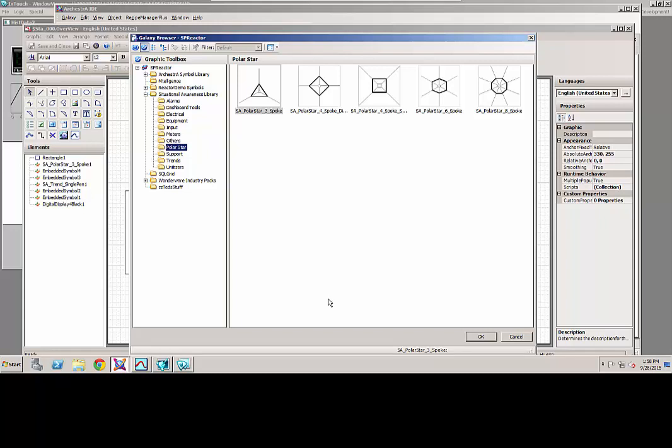So basically, a polar star is a very graphical representation of multiple variables, and as those variables change, you will see the actual shape change. So it gives the operator a very quick glance at the screen. They can see how variables relate to each other. Maybe in a normal situation, it's a perfect triangle like a three-star polar star or a six-spoke that it's all equal in variables. But if it's out of tolerance, you might see one spoke grow and one spoke shrink depending on the situation.